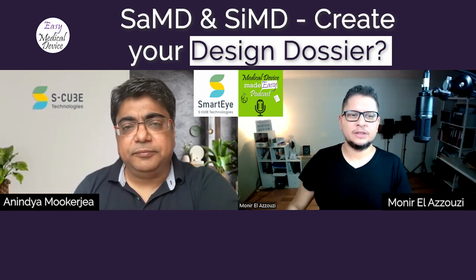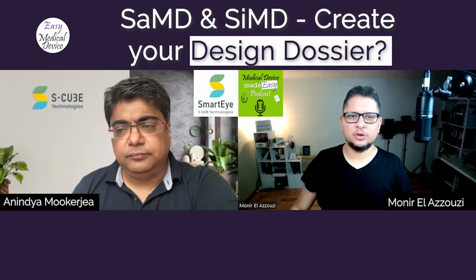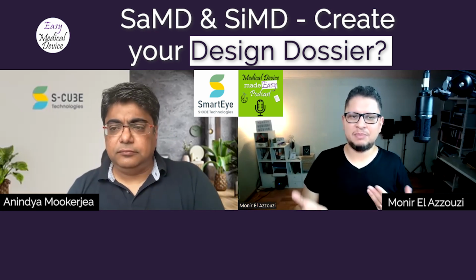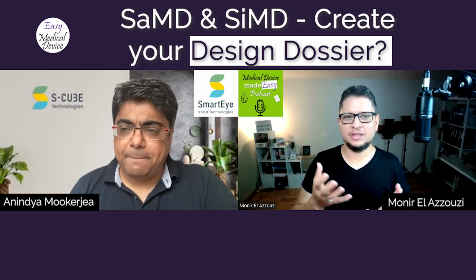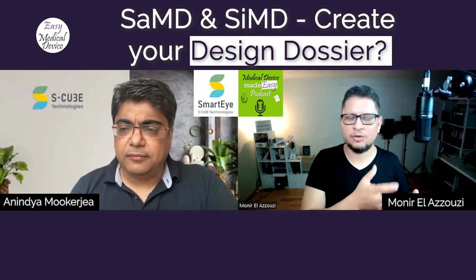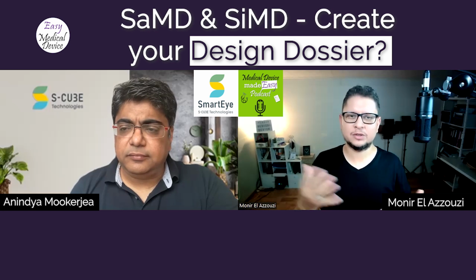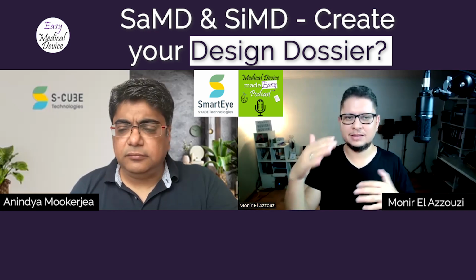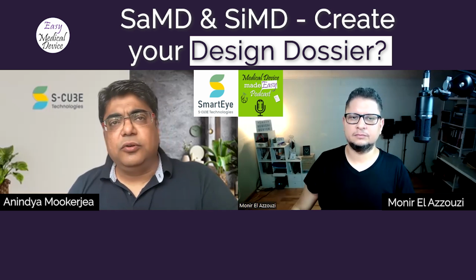And 62304, we had already an episode on the podcast about it. But today the objective is really to focus on one of the elements of the design, which is the design file, or design documentation, design dossier. So does 62304 explain how to develop this design file, or is it ISO 13485 that you have to use for that? Is there one that is leading the other? Yeah, sure. 13485 is the overall quality management system, which does not have a focus on software, but 62304 is the standard for software.